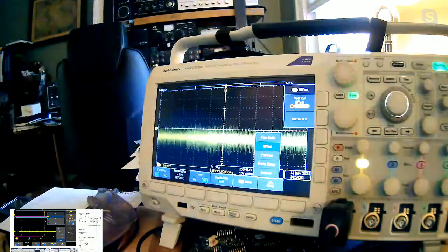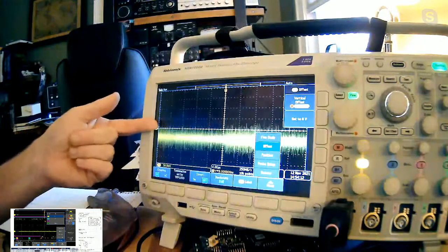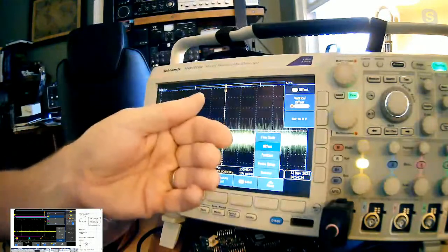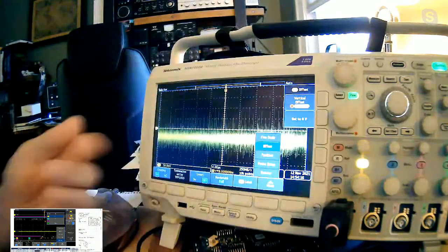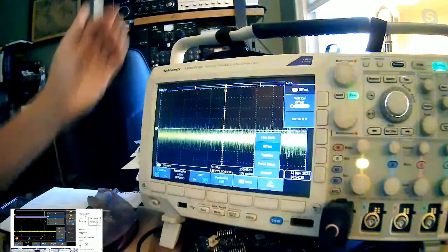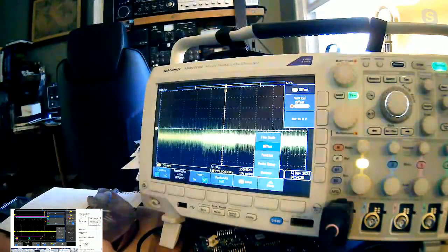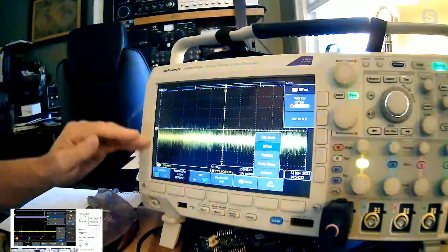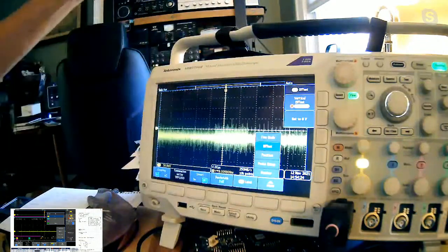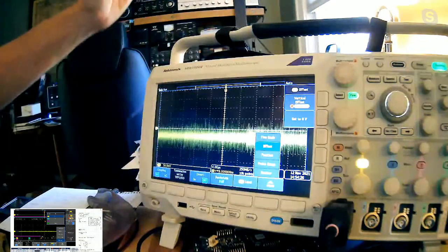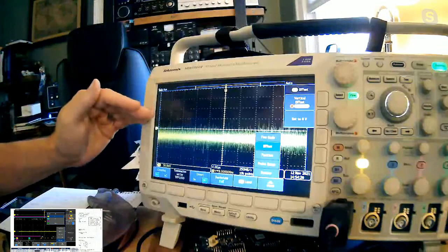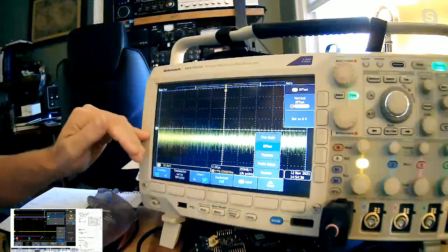Now, linear scopes don't really do this offset, right? You mean analog scopes, yeah. Yeah, analog scopes. They generally don't, because what we're doing here is optimizing what goes into the analog to digital converter. On analog scopes, generally the position knob has a lot more range. If the signal is 8 divisions above the screen, you probably have enough range in the position knob to bring that back down. On digital scopes, you don't have that.